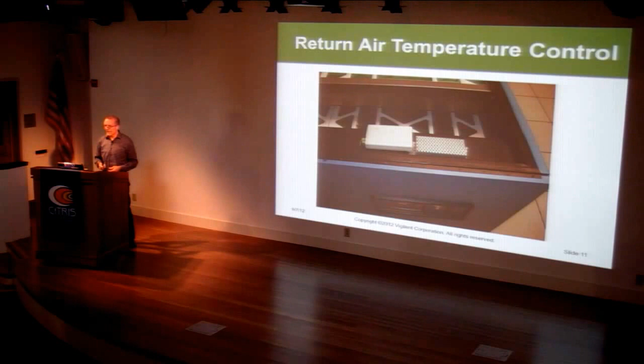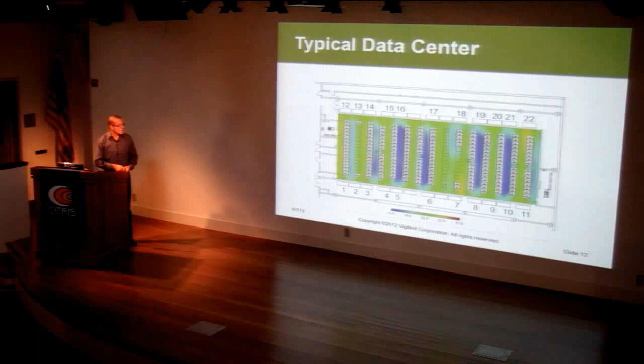I showed some pictures already - there are many of these units. This is a pretty typical mid-sized data center scenario: rows of racks here, maybe a dozen across, and air conditioners around the perimeter - this particular one has 22 of them. They're arranged with cold aisles and hot aisles, the blue being cold and the rest hot, right next to each other. Most of these data centers are like those photos I showed, completely open plan, and air follows the path of least resistance. So you end up with strong interaction between these units, which consultants and operators observe - you hear talk at conferences about fighting behavior and instability.